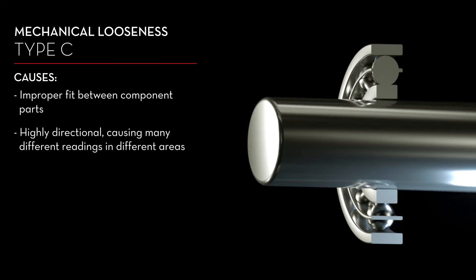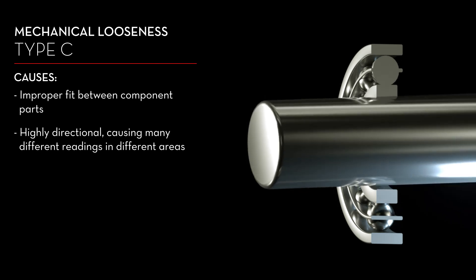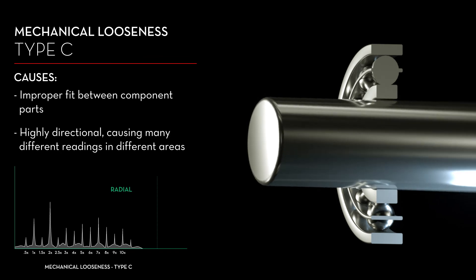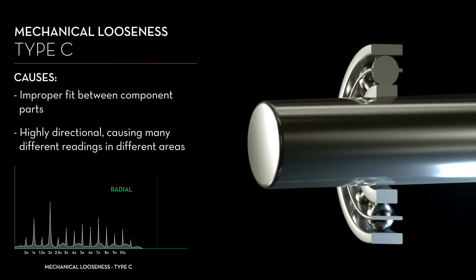Mechanical looseness is often highly directional and may cause noticeably different readings in different measurement areas around a bearing housing. Type C is shown on a spectrum as a high noise floor with many harmonic spikes.